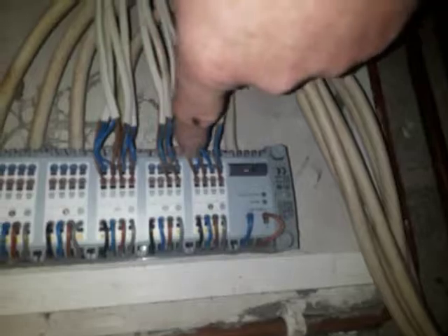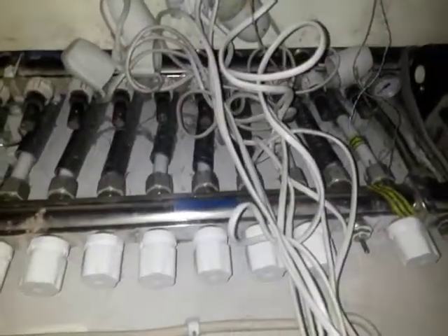As we turn this valve, we can see that the flow meter will go from about 2 there now, and there, that's shut off. So we have individual control of all the loops. The reason we do this is because some thermostats will turn on 2 and 3 and 4 loops at a time, so we can't easily determine, if we turn on one stat at a time, which loop goes where. Okay, so that's the first step, putting on these manual valves.